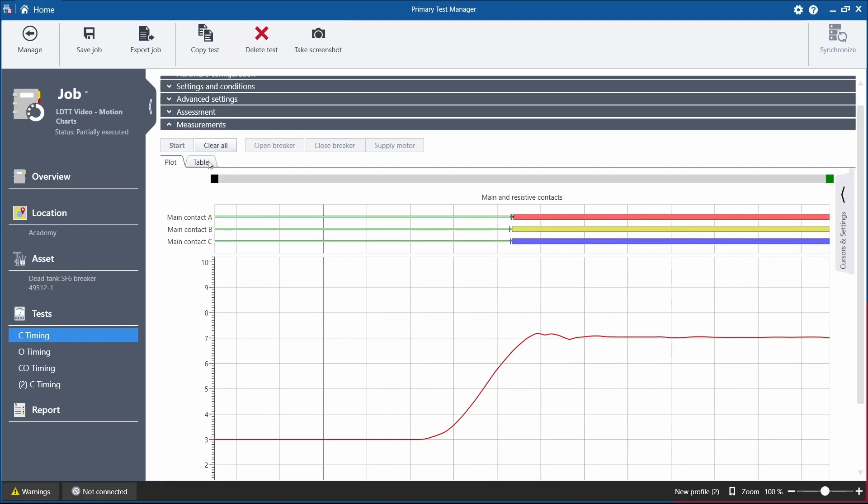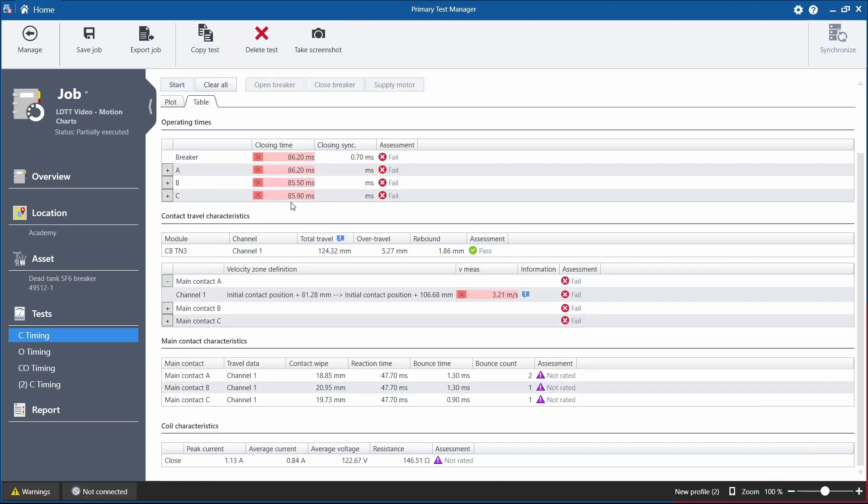If we move over to the table now, we have some characteristics of our measurement, like the closing time, how well each phase was synced together, some contact travel characteristics like total travel, over travel, and rebound, and the main contact characteristics: contact wipe, reaction time, and bounce time.